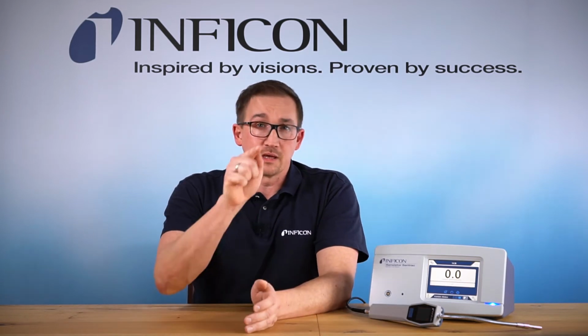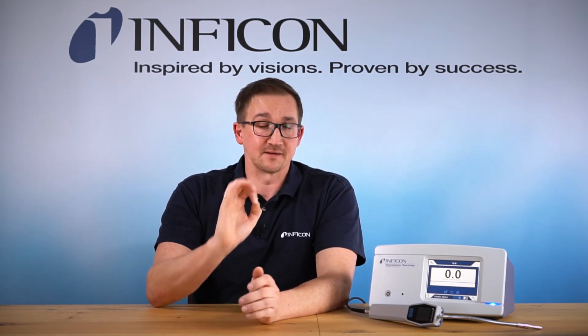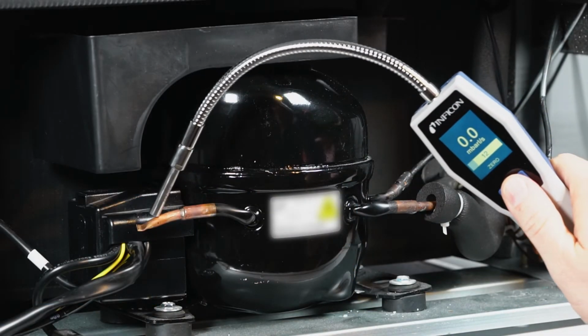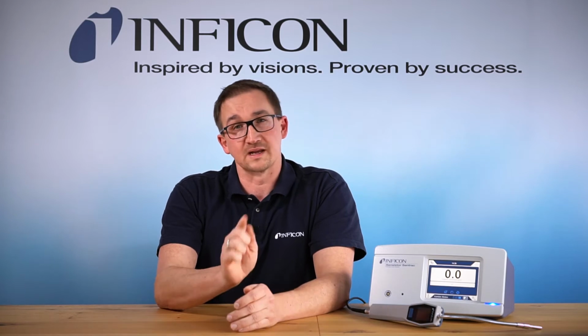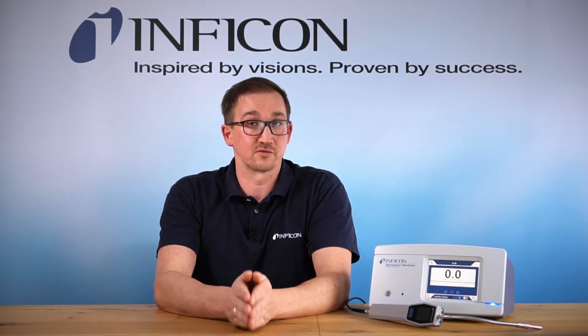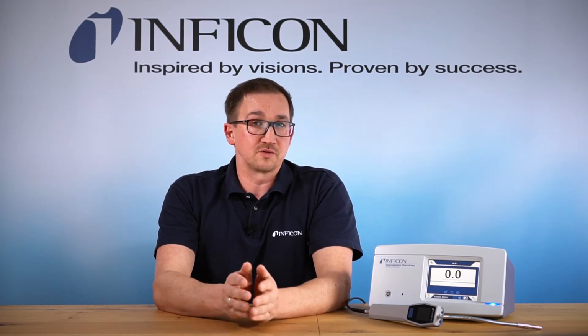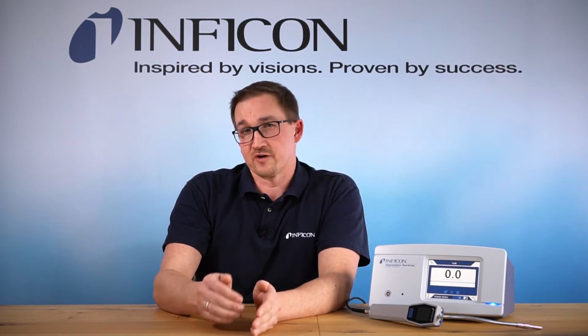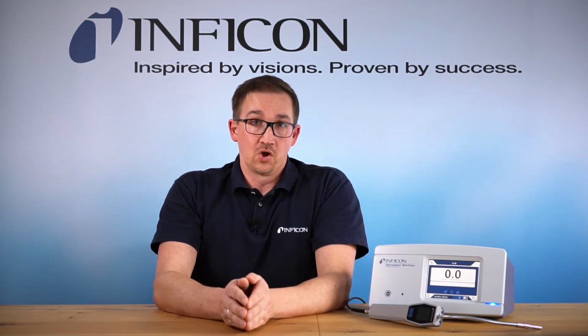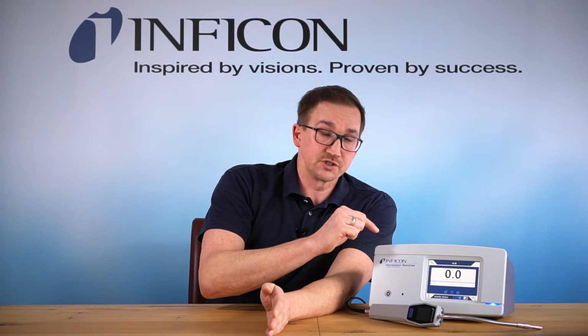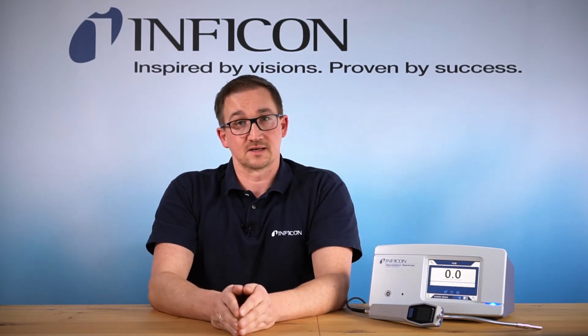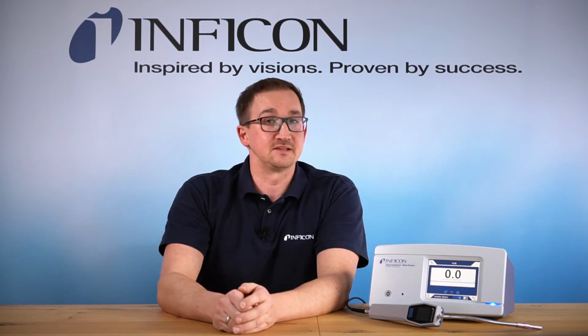So who benefits? Generally speaking, it is you, if you are looking for leaks in the 10⁻⁵ millibar per second range. In this case, the new Strix sensor gives you the extra reliability needed to find these small leaks accurately and consistently. When compared to Inficon's standard Sandtrack, the new Strix sensor shows significant improvements in process safety. Compared to older versions of hydrogen leak detectors, the new Strix edition is a real quantum leap. And now I'm going to demonstrate the difference in performance between our leading Sensistor Sentrac and the new Strix edition.